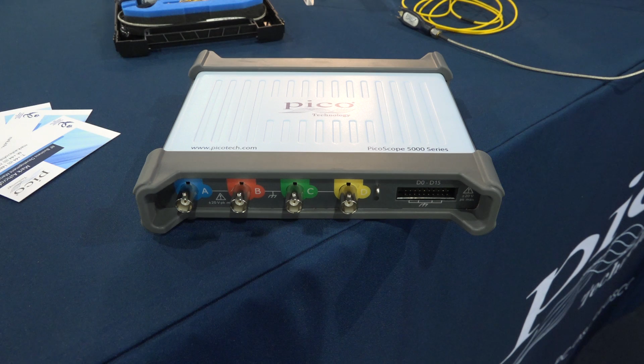One of the nice features of this unit is that unlike a normal oscilloscope where you will have a fixed resolution on all the 4 channels, they have this flexible resolution capability. So depending on the kind of bandwidth you're dealing with and depending on the kind of sample rates you're interested in, you can reconfigure the channels at a much higher resolution, all the way up to 16 bits. So if you are looking for a very high dynamic range, 80 dB of dynamic range analog performance, you can flash the firmware of this and create a single channel at 16 bits up to a certain frequency, and then you can get 80 dB dynamic range. Or if you're looking for 4 channels simultaneously, of course you can use it that way.